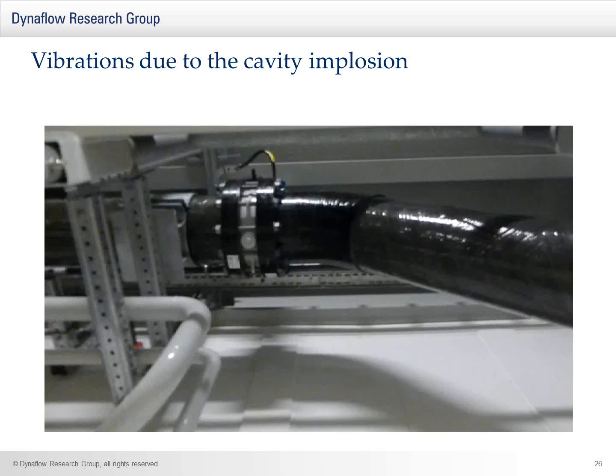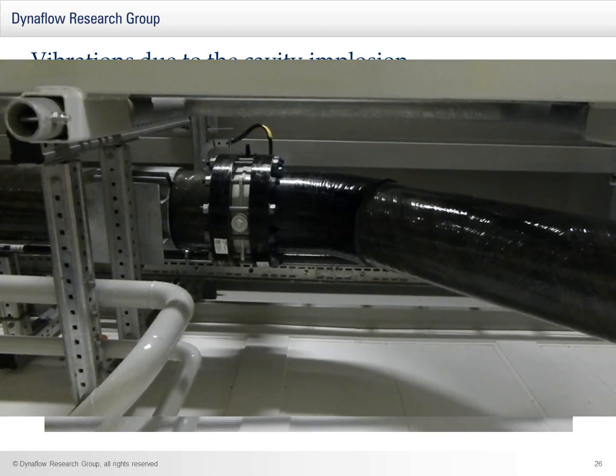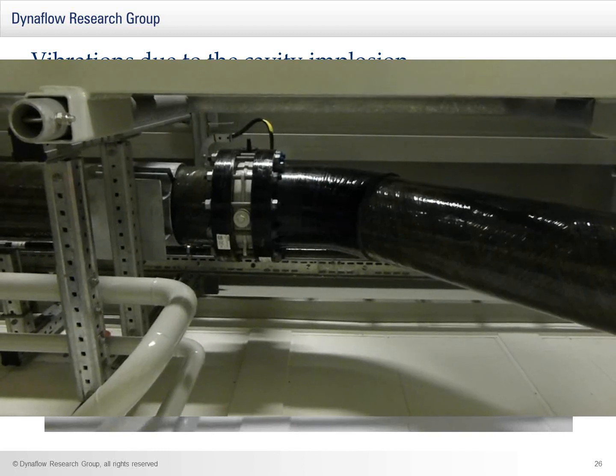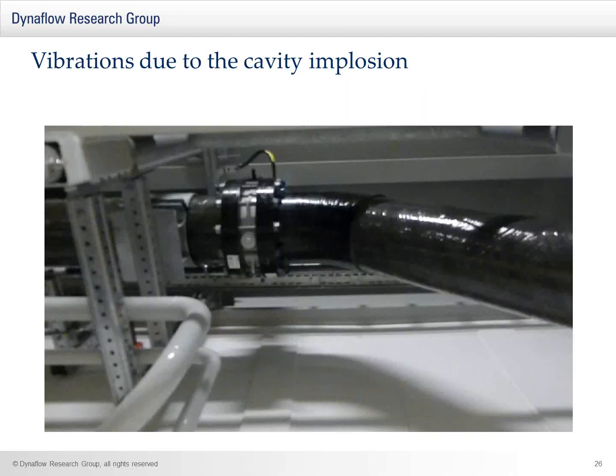Okay, let's play that again. What you saw there very clearly was the vibrations, and that you could noticeably see the vibrations due to the collapse of the cavity and the pressure peak passing through the system.